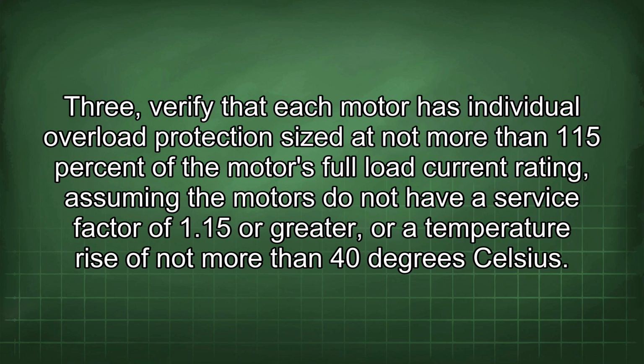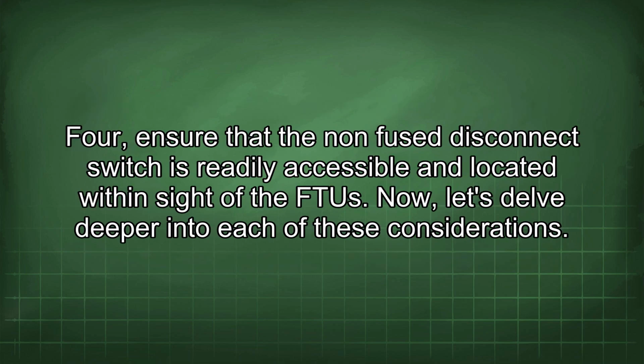3. Verify that each motor has individual overload protection sized at not more than 115% of the motor's full load current rating, assuming the motors do not have a service factor of 1.15 or greater, or a temperature rise of not more than 40 degrees Celsius. 4. Ensure that the non-fused disconnect switch is readily accessible and located within sight of the FTU. Now let's delve deeper into each of these considerations.